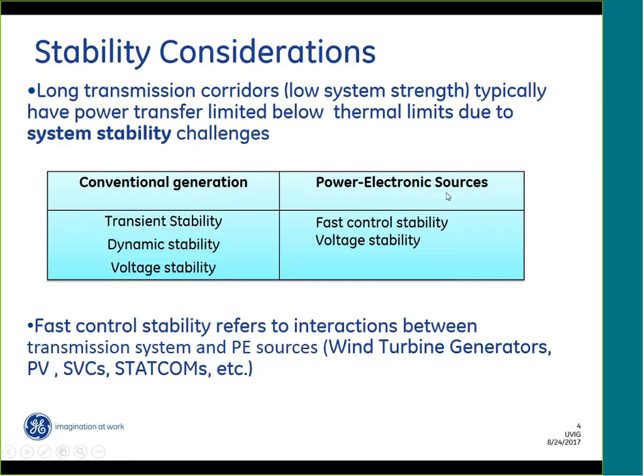In the case of power electronic sources, and I'm going to use the wording power electronic sources to refer to the sources that we just discussed in the previous page, the type of stability problems are different and manifest themselves differently. So one of the stability considerations that could limit the amount of power that can be transferred through a corridor is fast control stability. That would be the interaction between the transmission system and power electronic sources like wind turbines, PVs, SVCs. So different power electronic sources that have fast controls could interact, and that interaction could result in trips. So you would have to limit the amount of power that you inject in the system to avoid those interactions.